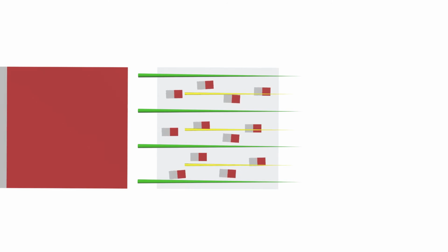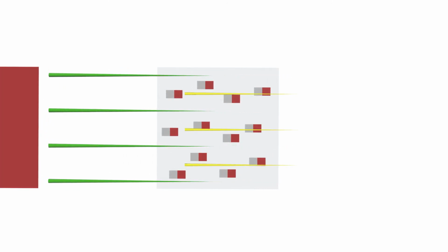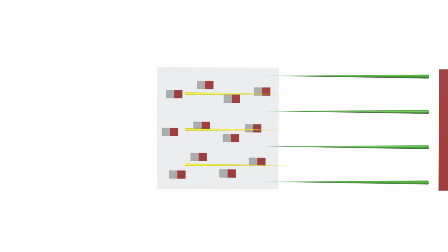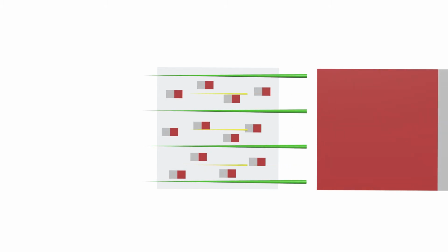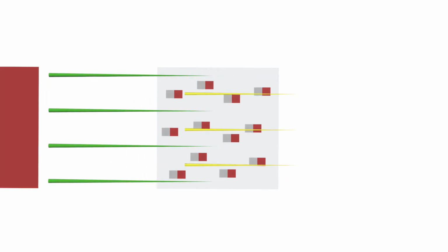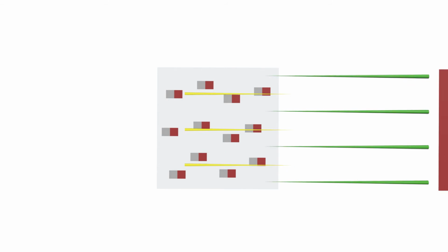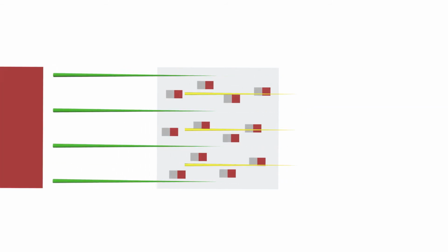And every time the magnetic field changes due to the alternating current variation, these small magnetic fields have to be aligned again. Which means an electrical transformer is losing energy due to this alignment every time the current changes. This is called hysteresis power loss. The higher the frequency of the alternating current, the higher this power loss is.